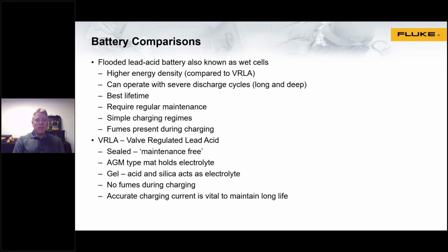Now, the VRLAs, they're sealed. They're the so-called, and I'll use air quotes because I'm on video, maintenance-free batteries. So there are two different types. In the AGM type, a mat actually holds the electrolyte. And in gel type batteries, there's a silica that acts together with the acid as the electrolyte. The pluses there, no fumes during charging. However, you have to have accurate charging current to get the best possible life out of that type of battery. You'll run into both types out in battery backup systems.